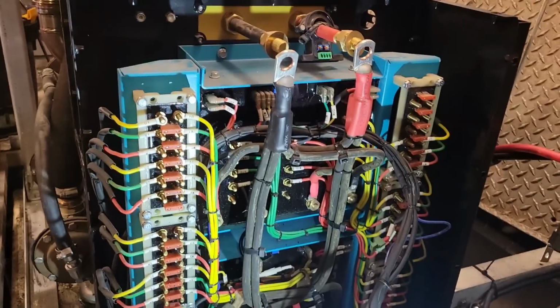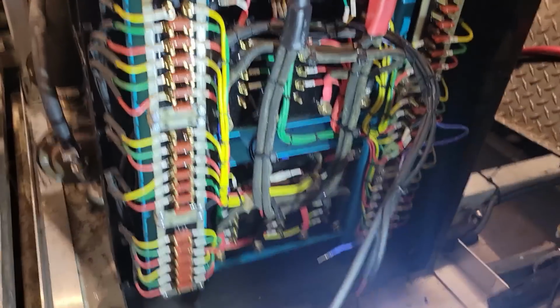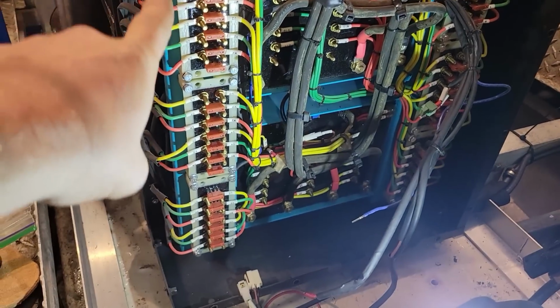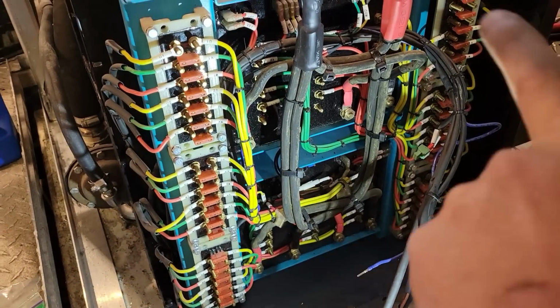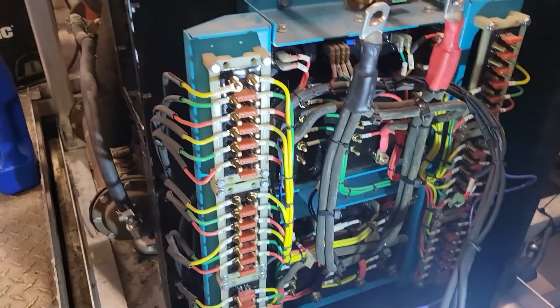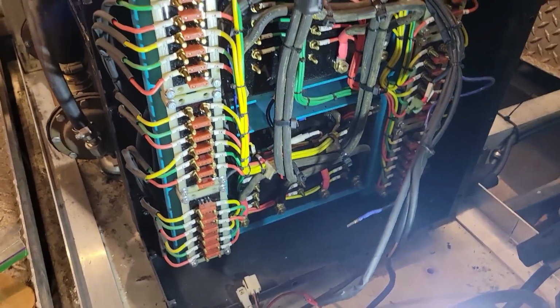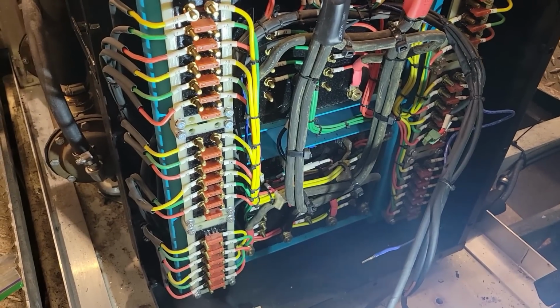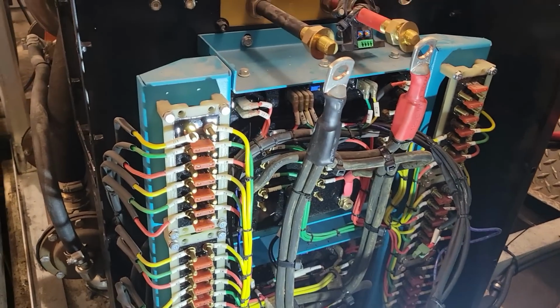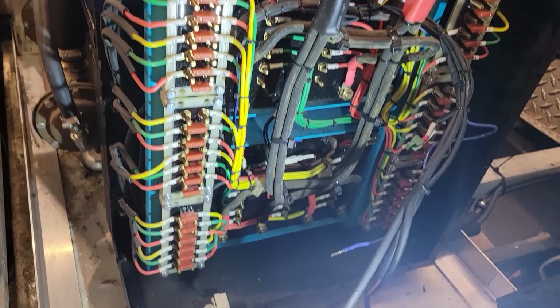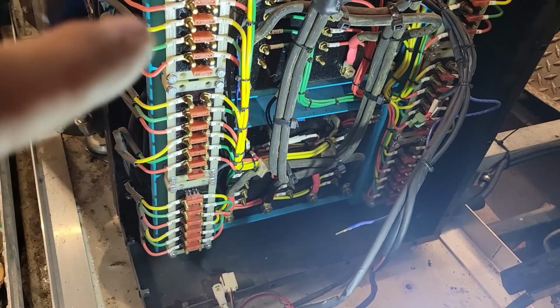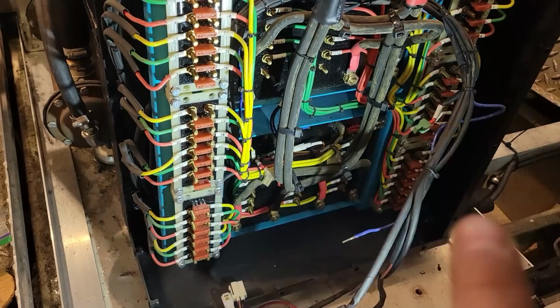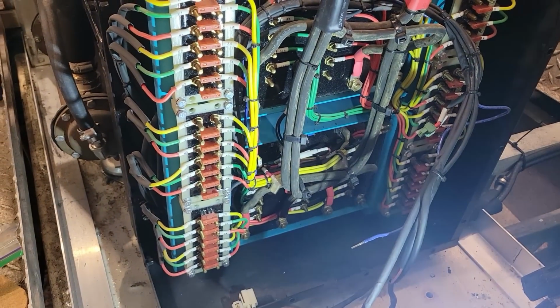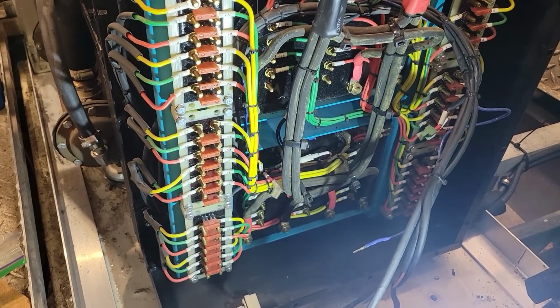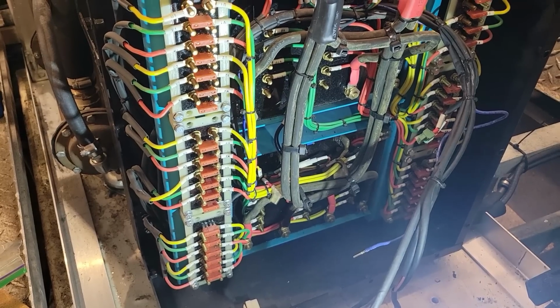This is what they look like. All these wires running down the sides here and over here are coming off the stator in the generator, and I've got to extend those to wherever I'm mounting the rectifier modules. I have to take every single wire loose on the outside, lengthen it, and move it over to where I'm putting the modules.